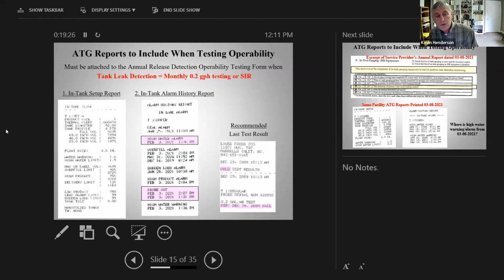And so you see the in-tank setup obviously should be part of that, what you're looking at. The alarm history report is an important part of this. This happens to be the in-tank alarm report because, again, we're looking at the probe itself. If you know the Veeder-Root, you know that there are several different alarm history reports. This one happens to be the in-tank alarm, which will give us the record of the high water alarm and the probe out alarm that we're looking for to show that, yes, we did pull the probe out. Yes, we did verify that the floats are reading correctly, or at least appear to be.